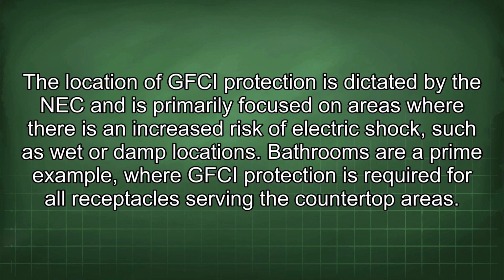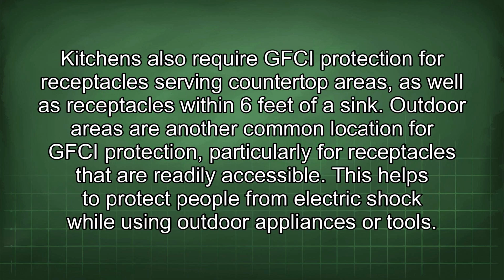The location of GFCI protection is dictated by the NEC and is primarily focused on areas where there is an increased risk of electric shock, such as wet or damp locations. Bathrooms are a prime example, where GFCI protection is required for all receptacles serving the countertop areas. Kitchens also require GFCI protection for receptacles serving countertop areas, as well as receptacles within 6 feet of a sink.